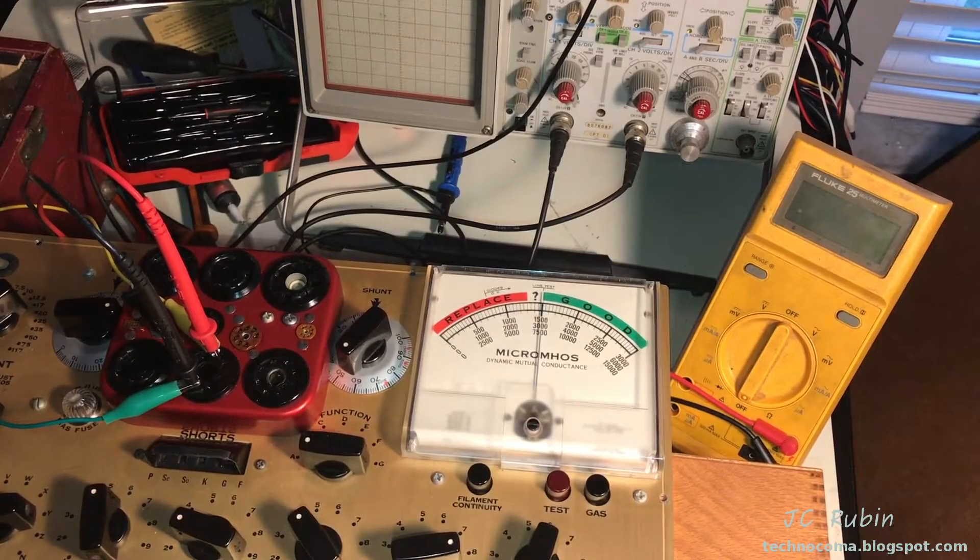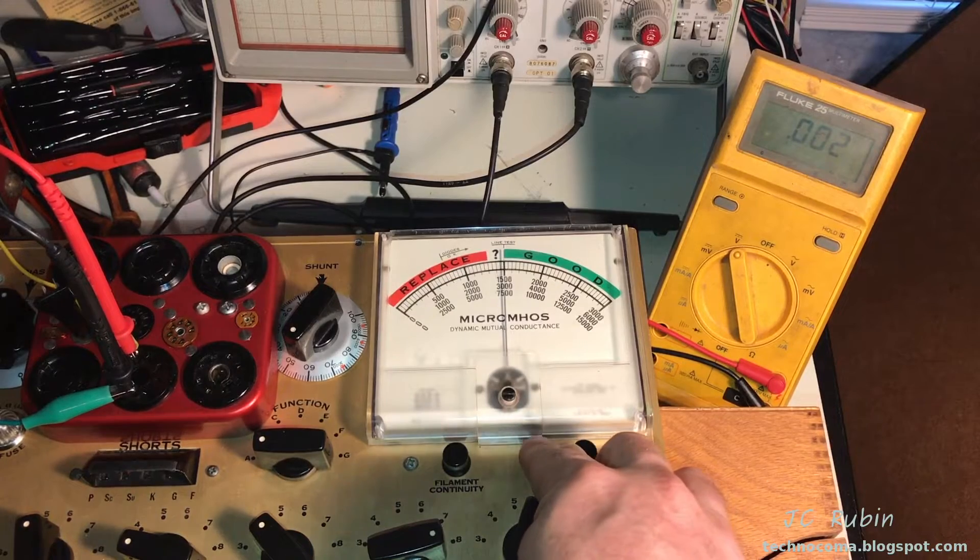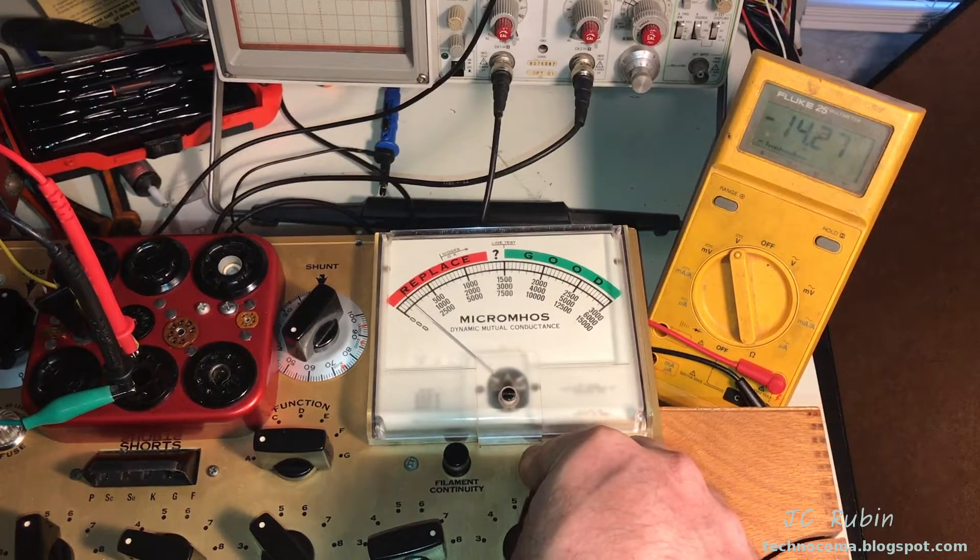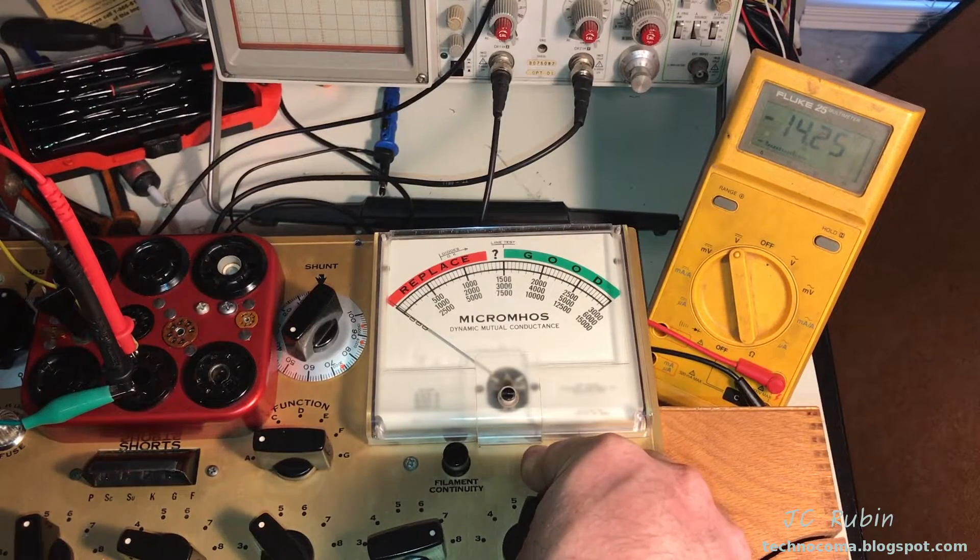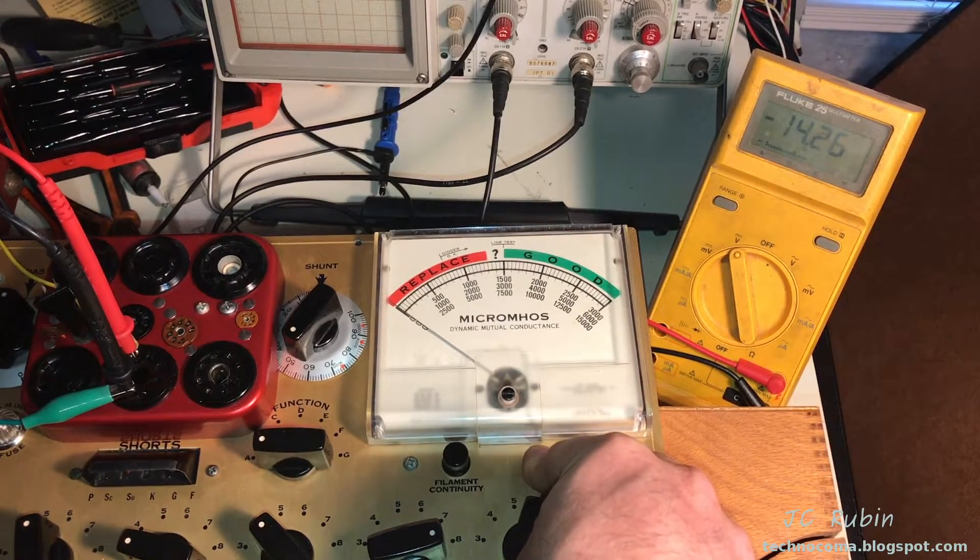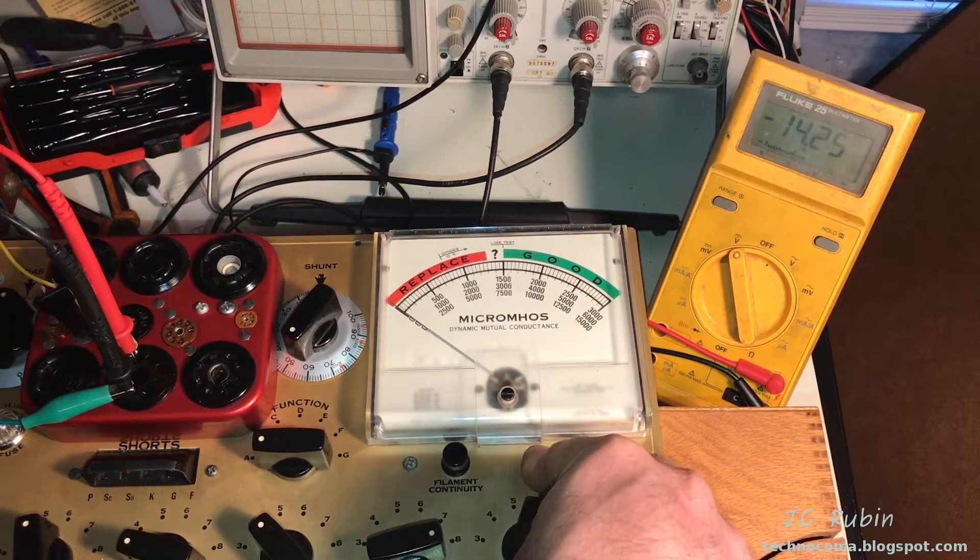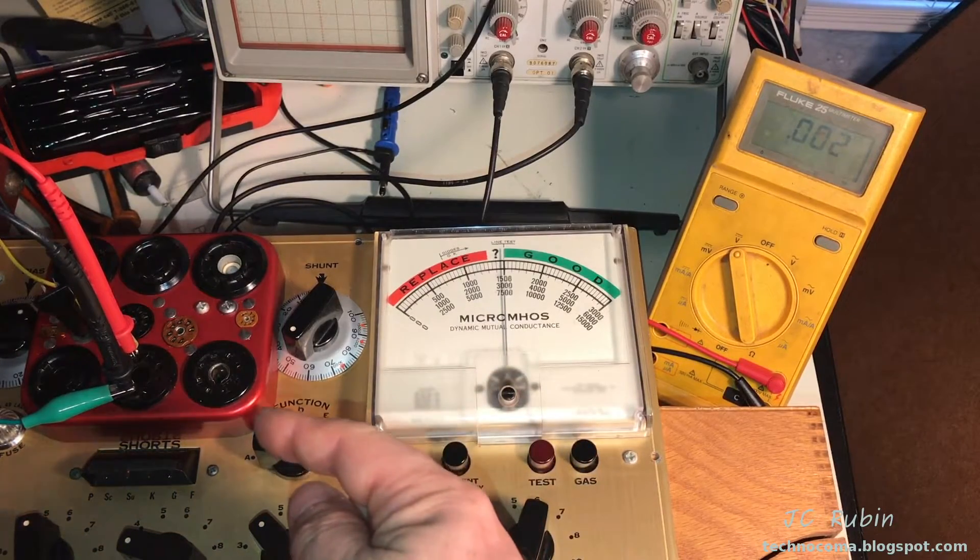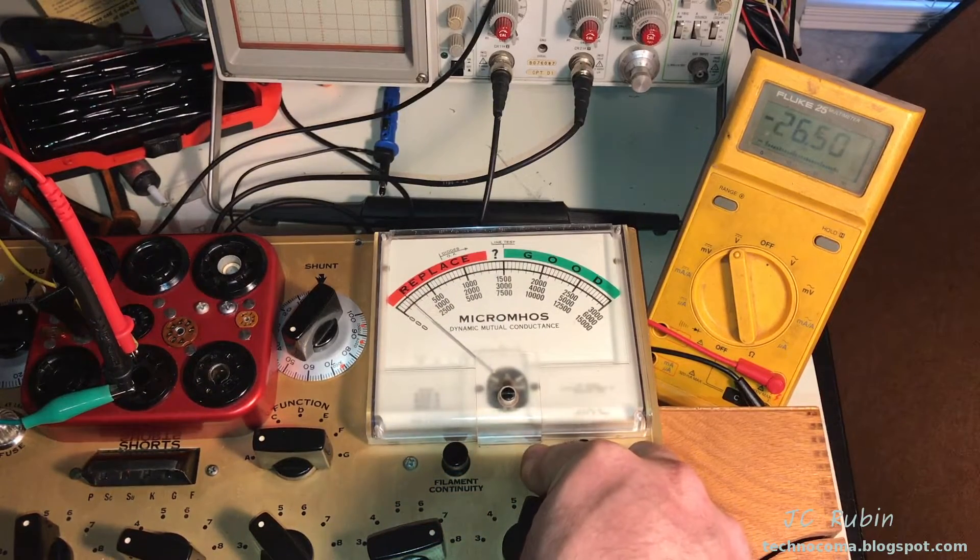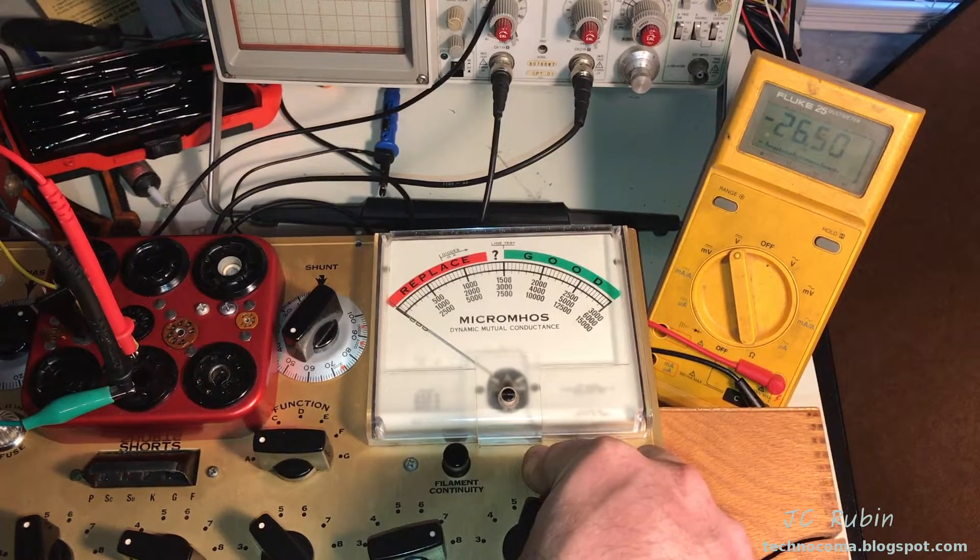The next two tests will use a 50k shunt again. Next value has the bias knob at 50. I'm going to push the button, and we're supposed to get 13.4 plus or minus 1 volt. This is within tolerance, so this value is good at 50. Next one is 75 on the bias knob, uses the same 50k shunt. It's supposed to be 25.8 plus or minus 1 volt. We're seeing 26.5, which is also within tolerance.